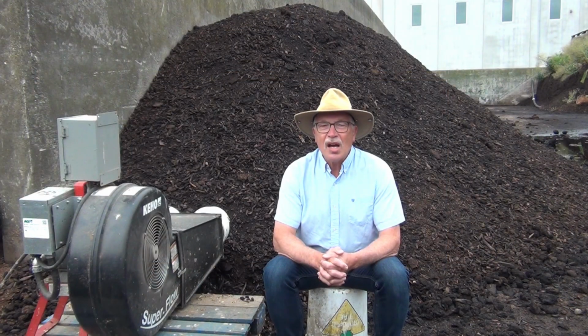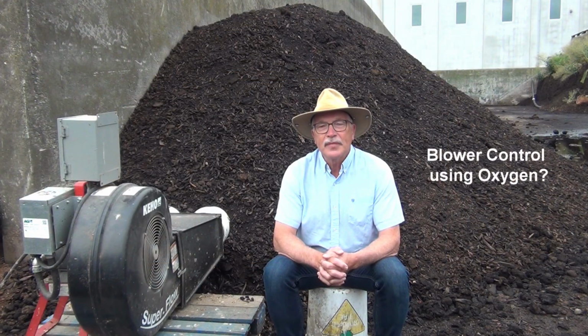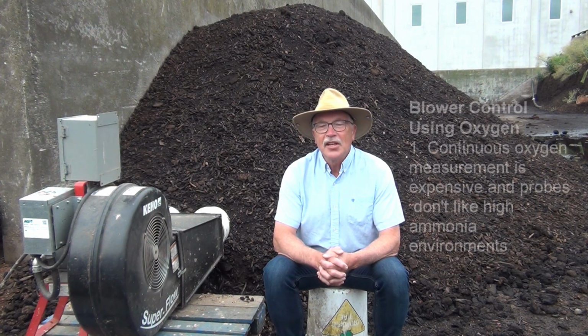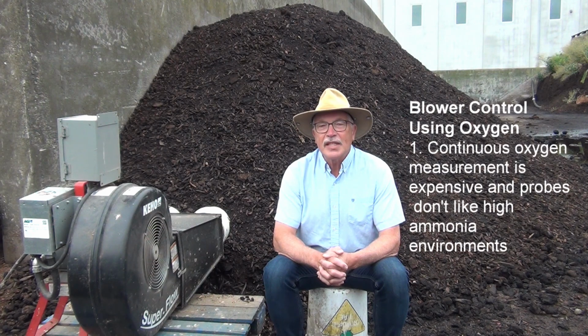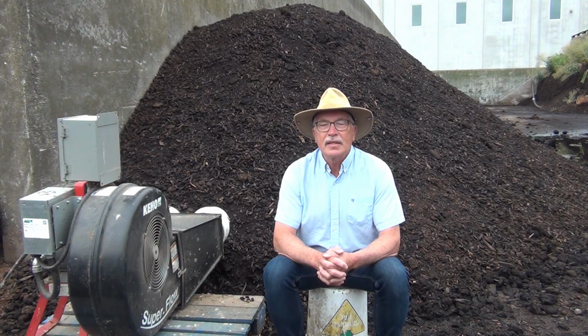But what about using oxygen to control the aeration? I talk about the importance of oxygen for the microbes, so why don't we use oxygen as a control mechanism? There are four things to think about with controlling blowers using oxygen. First, oxygen probes for continuous monitoring are very expensive and prone to fail, especially in high ammonia environments.